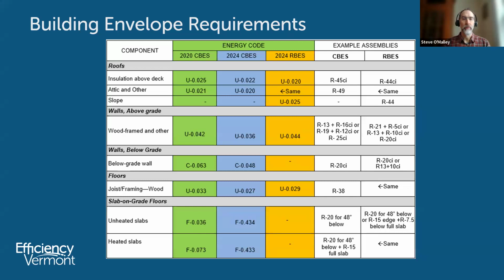Let's see, what else do we have here. Below grade wall: in the energy code there's a C factor, 0.048 for instance for the 2024 CBES, and you'll notice the example assembly is R20 continuous insulation under CBES. The C factor is not the same as a U factor. A lot of us have calculated U factor for an assembly, but you can't do that with a C factor, it's not the same analysis. That would involve more modeling-type software, because it takes into account things like soil gradient temperatures, not simple linear math we can do on a calculator.